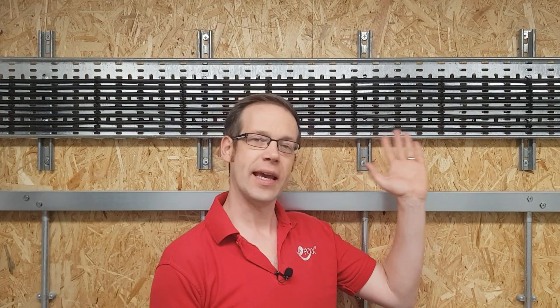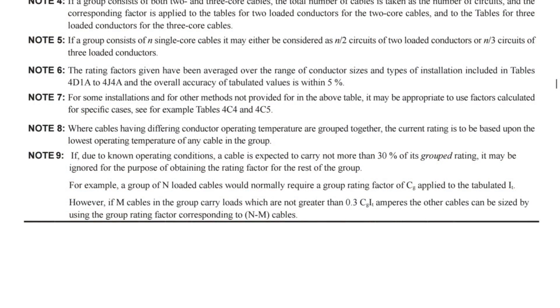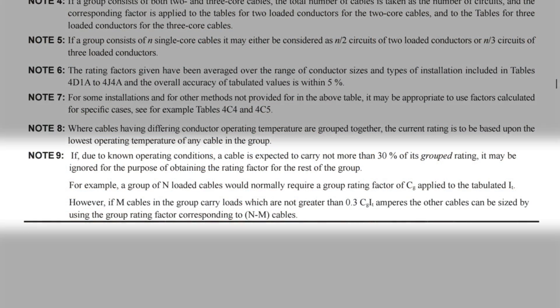In this case, do we really need to use all eight cables to figure out our grouping factor? Well, there is a way that may allow us to discount some of those conductors. Note 9 to the table sheds a little bit of light on this. It reads: if, due to known operating conditions, a cable is expected to carry not more than 30% of its group rating, it may be ignored for the purpose of obtaining the rating factor for the rest of the group.